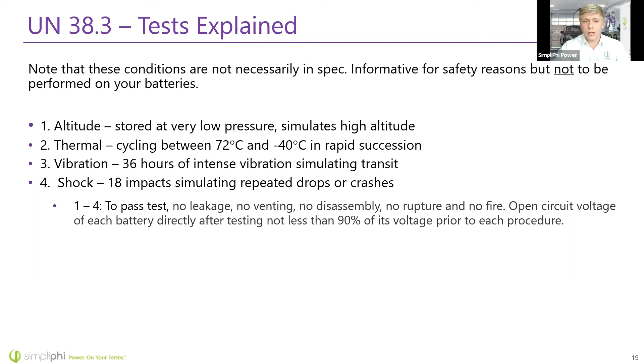To pass this test, they're not exactly testing for operation of the battery. They're not necessarily checking capacity, but they are testing that there's been no leakage, venting, disassembly, rupture, fire, and no significant change in open circuit voltage. This means they're making sure there's been no disasters and no major change to the layout of the battery, nothing disconnected or short-circuited during this time.